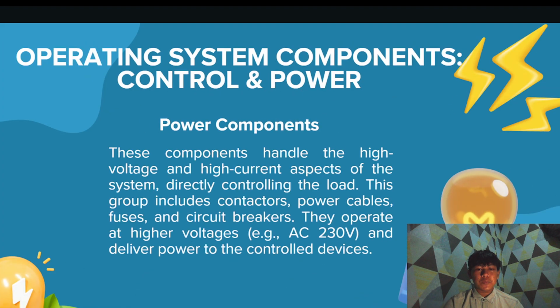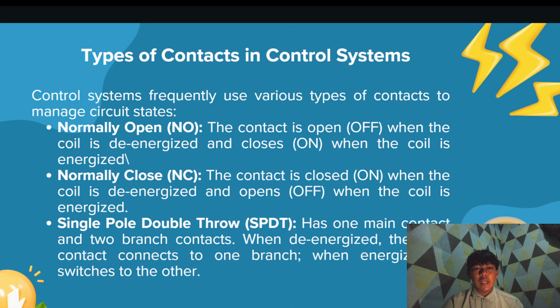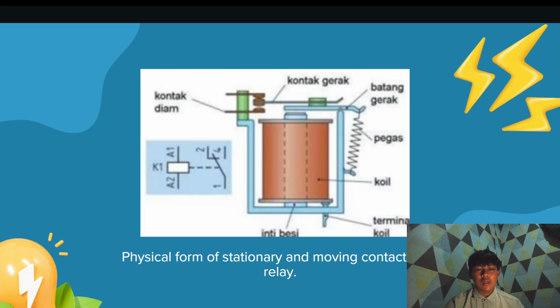Power components handle the high voltage and high current aspects of the system, directly controlling the load. This group includes contactors, power cables, fuses, and circuit breakers. They operate at higher voltage and deliver power to the load. Types of contacts in control systems. Control systems frequently use various types of contacts to manage circuit states: normally open, normally closed, and the last, single pole double throw. And this is the physical form of stationary and moving contacts in a relay.